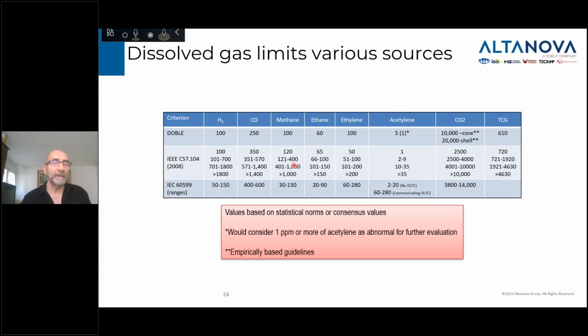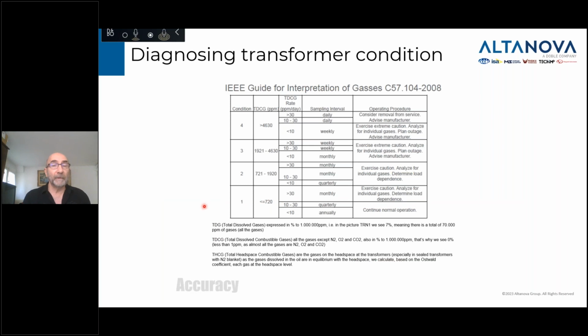There's a couple of reasons. One is that people often use the first level to set up the alarm limit on their online monitors. So when you have an online multigas monitor and you're trying to set up the warning alarm, people often use the IEEE numbers on what we call the first level. And potentially you can use the second level to set up your critical alarm, or usually maybe use lower numbers. Each of those levels in the IEEE is attached to a sampling interval and an operating procedure.